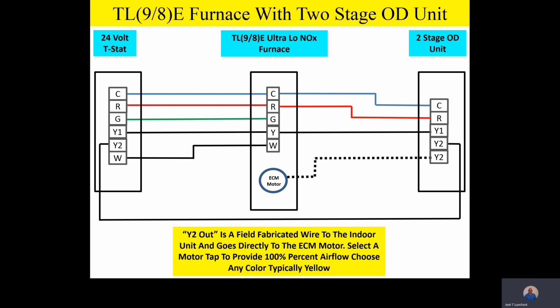And so that Y2 out from the outdoor unit will come in, and again, we have to field fabricate that wire. It's just 24-volt, low voltage wire. It's just very, very simple. And you just put a spade connector on the end of it on the inside. So you bring that wire in, put a little spade connector on it, and then attach it to a motor speed tap that gives us 100% airflow. Now, team, remember one more time, we want to make sure that that 100% airflow is 400 CFM per ton. So if I have a 2-ton unit outside, that 100% airflow needs to be 800 CFM and so on.